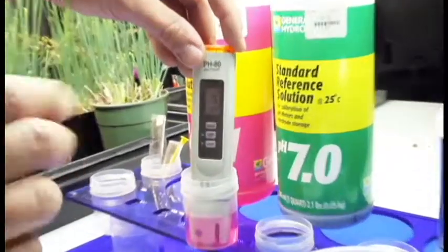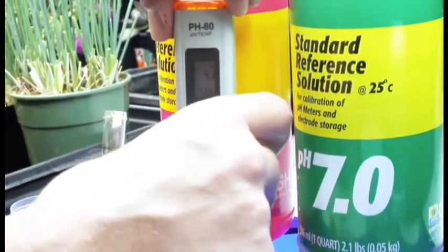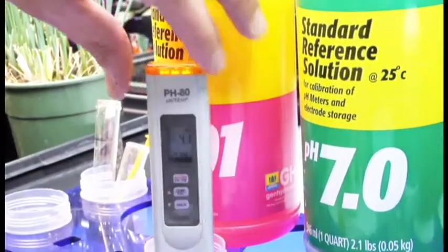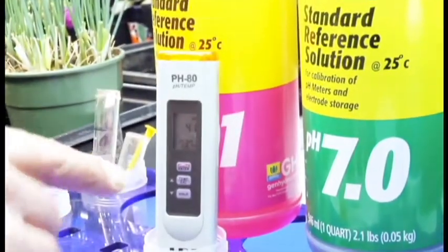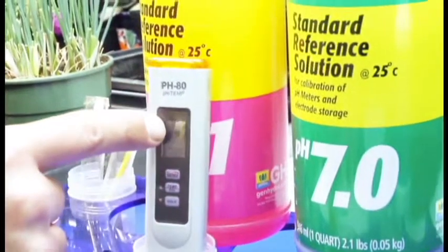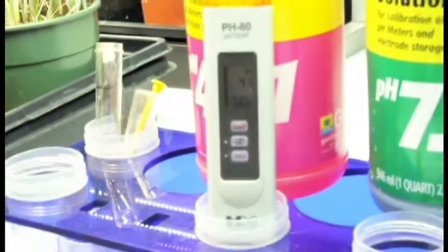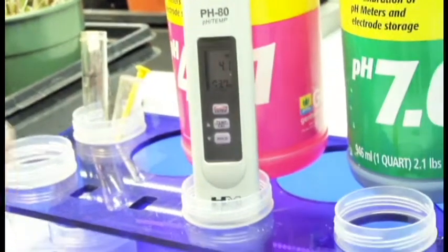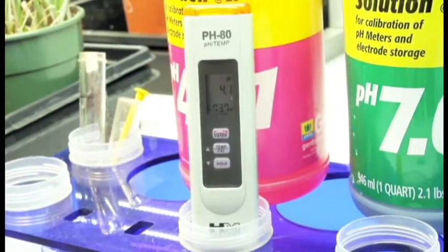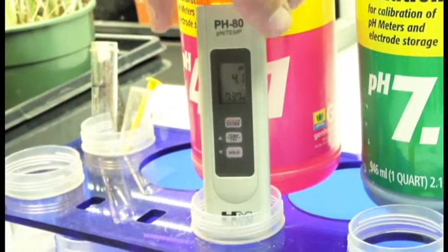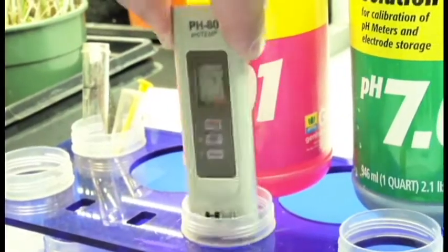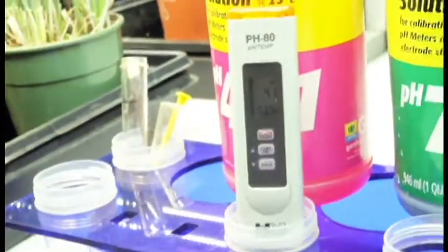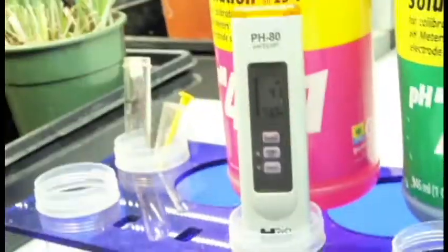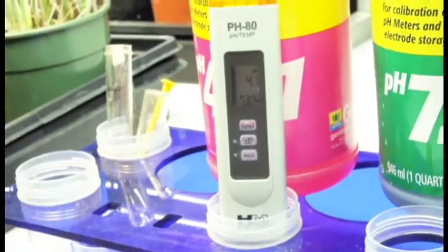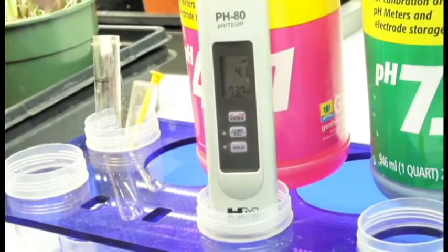Within generally about 30 seconds this thing is set. I'm going to set it back down so you can see my numbers and see what I'm seeing. Right here I'm paying attention to the temperature and the pH. Since temperature basically affects pH, once the temperature quits moving, then I know my meter is pretty much where it's going to be and I can begin the calibration process. I'm going to give it one more quick stir, check that my temperature hasn't moved and it's stable. It looks pretty stable. It's reading 4.1, which is really close to 4.01, but it's still not the same.